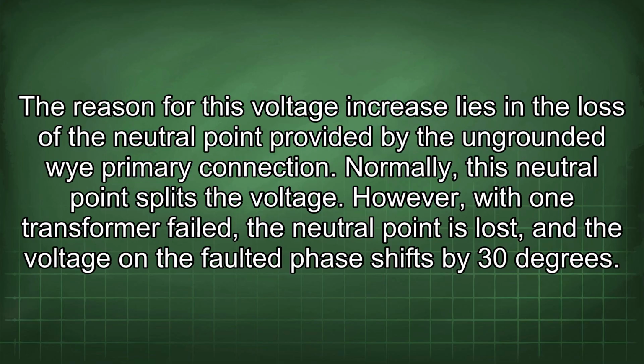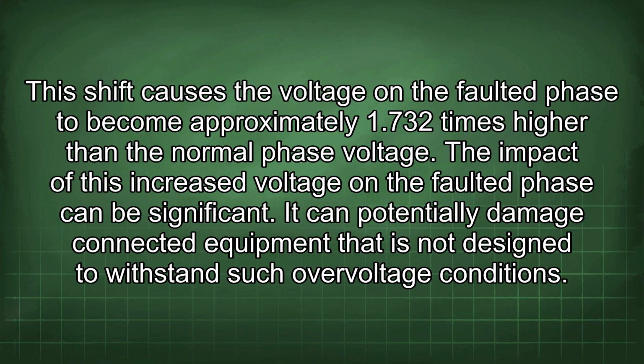primary connection. Normally, this neutral point splits the voltage. However, with one transformer failed, the neutral point is lost, and the voltage on the faulted phase shifts by 30 degrees. This shift causes the voltage in the faulted phase to become approximately 1.732 times higher than the normal phase voltage. The impact of this increased voltage on the faulted phase can be significant. It can potentially damage connected equipment that is not designed to withstand such overvoltage conditions.